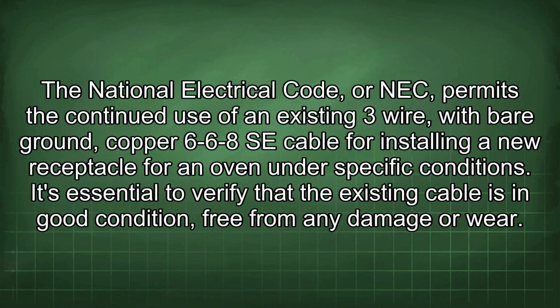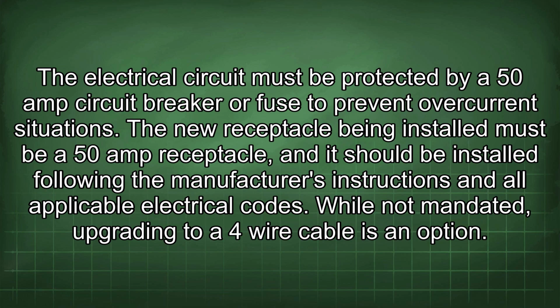The National Electrical Code, or NEC, permits the continued use of an existing 3-wire with ground copper 6-6-8 SE cable for installing a new receptacle for an oven under specific conditions. It's essential to verify that the existing cable is in good condition, free from any damage or wear. The electrical circuit must be protected by a 50-amp circuit breaker or fuse to prevent overcurrent situations.